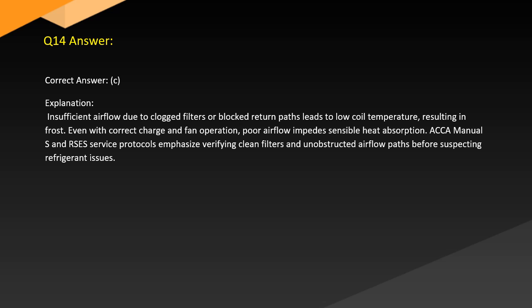Answer. Correct answer: C. Explanation. Insufficient airflow due to clogged filters or blocked return paths leads to low coil temperature, resulting in frost. Even with correct charge and fan operation, poor airflow impedes sensible heat absorption. ACCA Manual S and RSES service protocols emphasize verifying clean filters and unobstructed airflow paths before suspecting refrigerant issues.